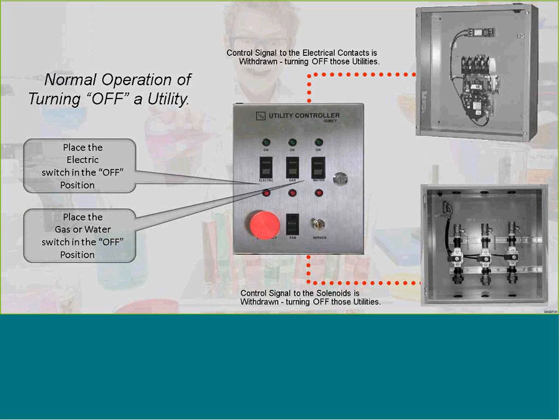The panic button is not required to shut the system down. We don't recommend using the panic button except in an emergency situation, especially if you're tied into the fire alarm panel, because you don't want to send a false signal. When we send a signal to the fire alarm panel, we don't activate it—all you're doing is sending a supervisory signal letting someone know something's going on in that room.